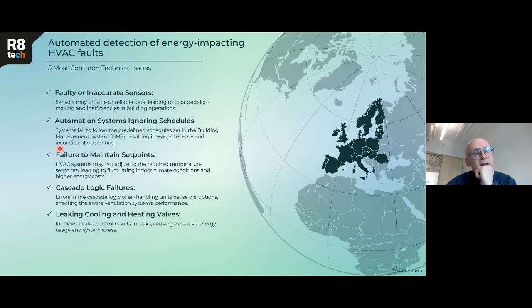Automation system ignoring schedules. It's very common, and it will cause additional consumption, and actually these faults could very easily offset our savings. So this concerns the ventilation systems, which have their own internal controller. These systems can be controlled by the ventilation system's own controller or through the BMS. The schedules are different, so they are not following the BMS schedule. And we're trying to find these kinds of issues.